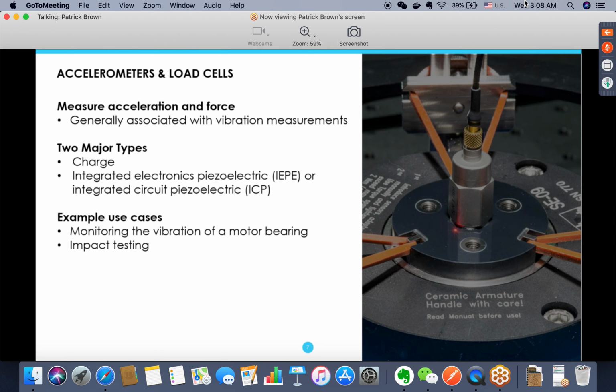You'll have just the resistivity of the wire itself causing issues. IEPE, due to the much higher voltage, is not really affected by that, and I've seen cables that have gone over 100 feet without any issues.